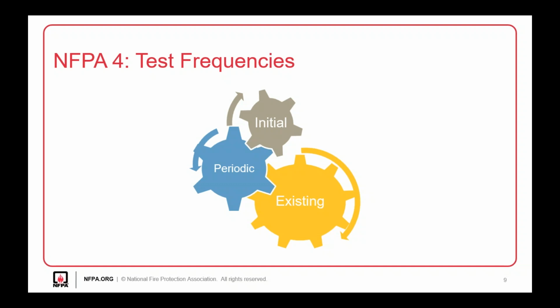When it comes to periodic testing, the concept of mandatory fixed integrated system testing was very controversial, and the committee discussed intensely requiring it every 5 years. But when you consider different buildings, like a hospital versus an office, it seemed irrational to impose that cost on the owner every 5 years regardless of building type. So rather than prescribing a fixed period, a project-specific frequency is required to be developed and identified in your test plan in accordance with NFPA 4.